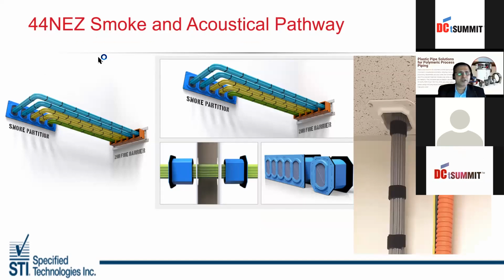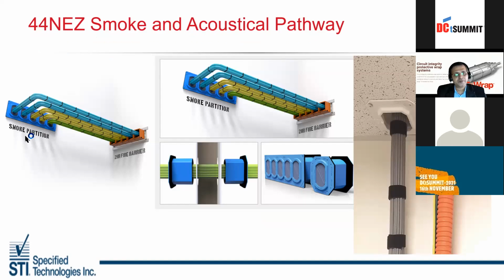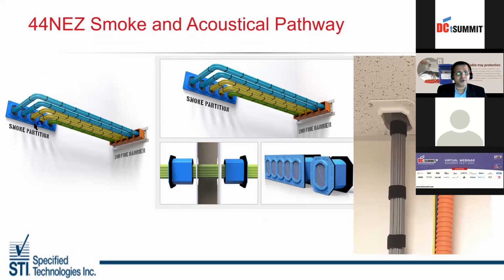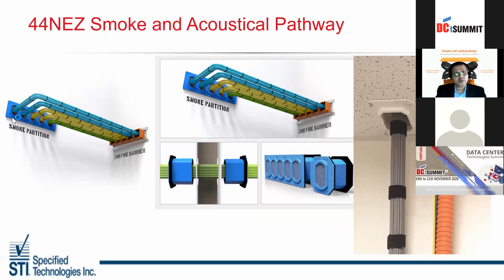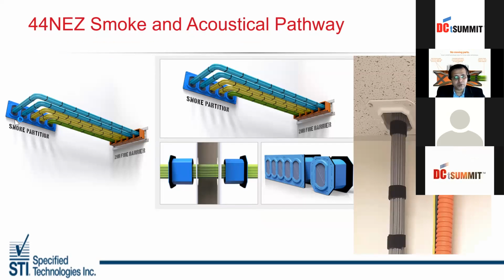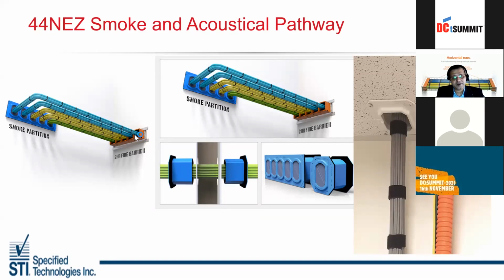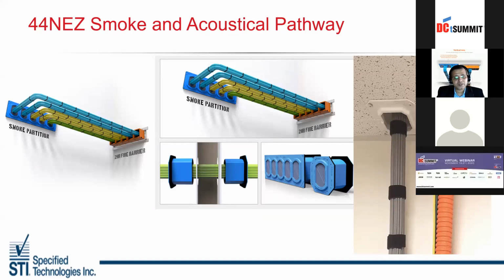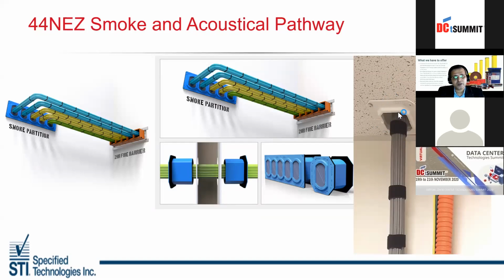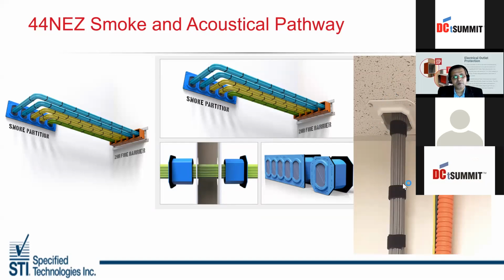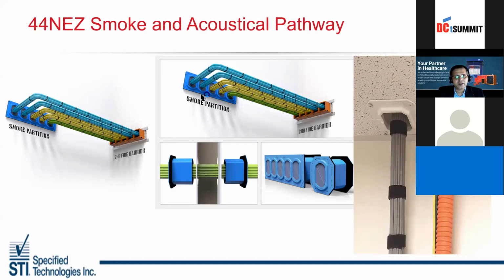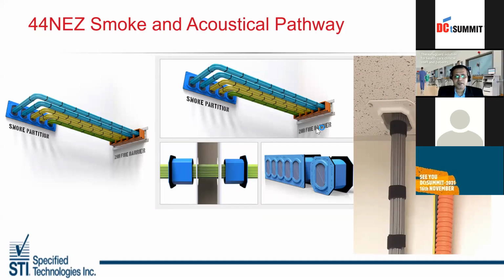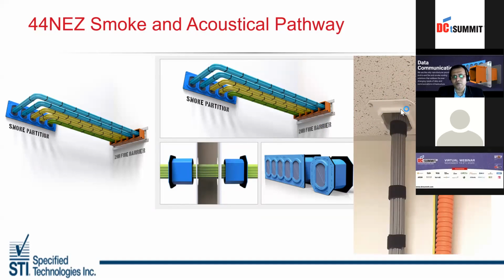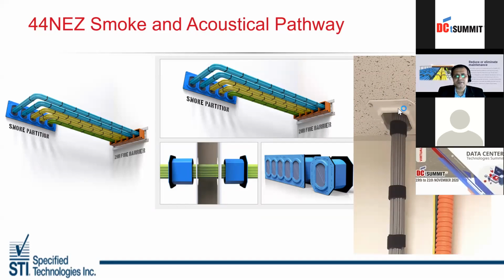We have smoke as well as fire barrier. Now, towards your left-hand side, it's a smoke partition, a non-fire rated partition. And towards your right, in the same scenario, you have a fire rated wall. In a smoke partition, this device will act as a smoke as well as a cable pulling device. And this will act as a fire as well as a cable pulling device. Here, towards your right-hand side, it's a false ceiling, and the smoke cabling device is installed. The cables can be pulled and pushed easily through these scenarios and taken above the false ceilings. It's very easy to install, and it comes in 2 different colors, blue or white. As of now, we have these 2 colors.